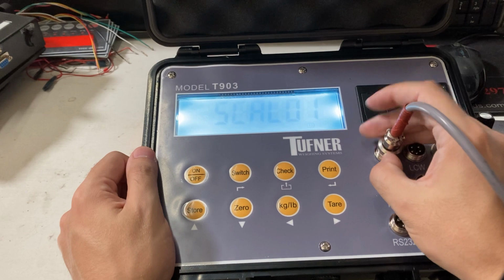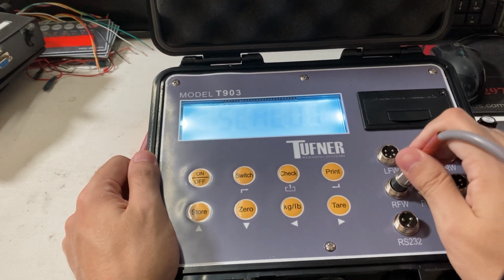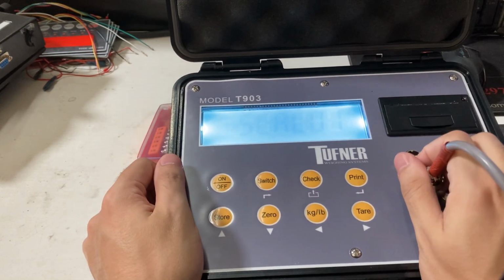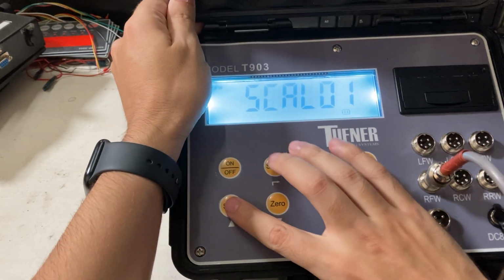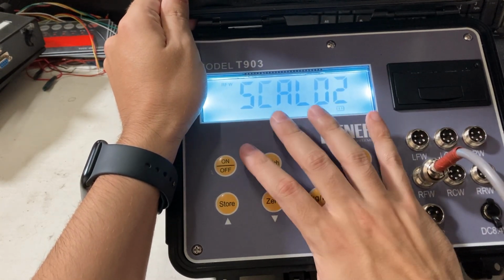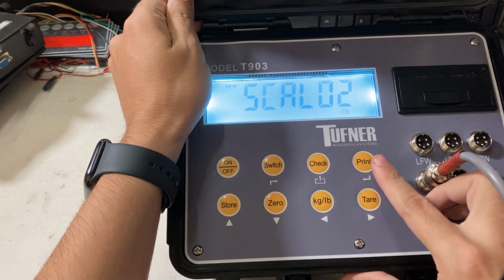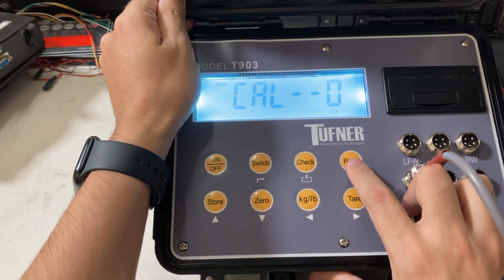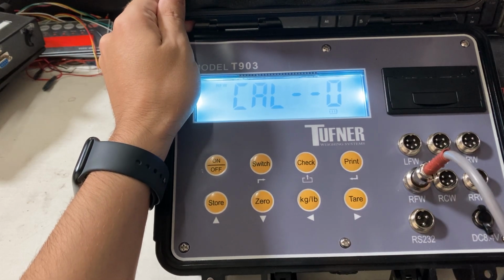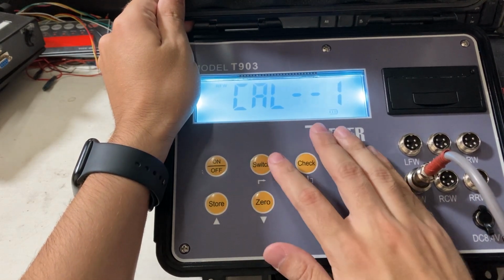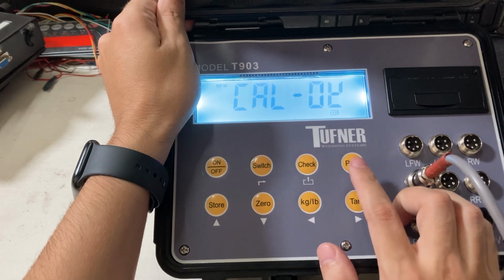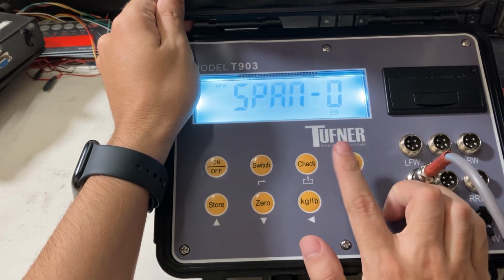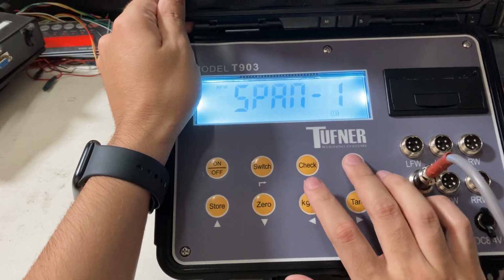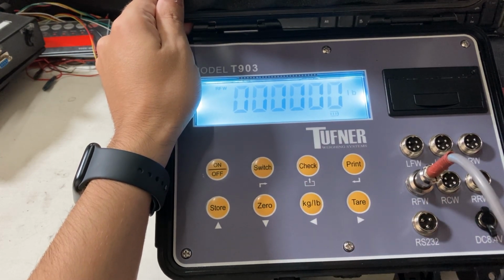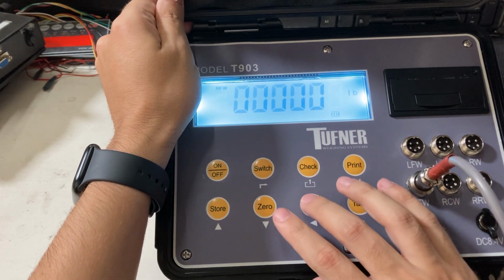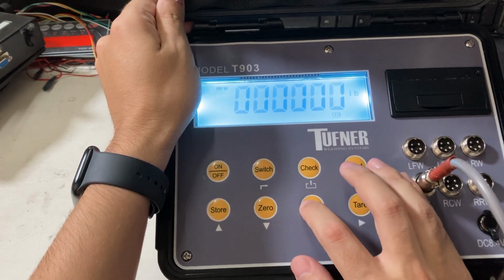So I'll show you that again. So I'll just move it over. This is number 2. Scale 2, RFW. That's the one I haven't plugged in. Cal 0. So make sure there's nothing on the scale. Made that to 1. Yes. Span 0. So make that to 1. So span means I am putting my calibration weight. So just on that one pad, I'm adding 1,000 pounds.